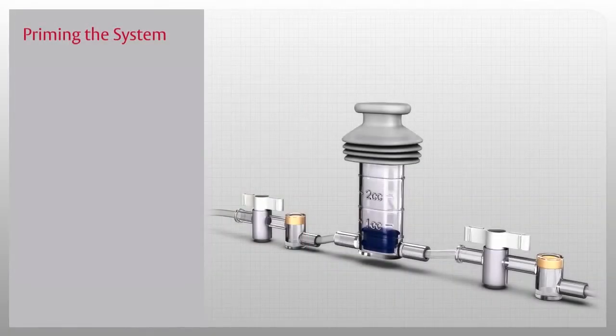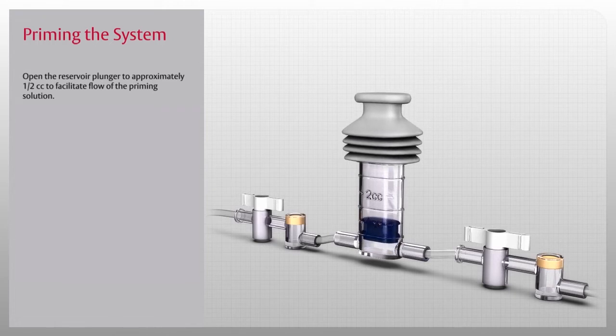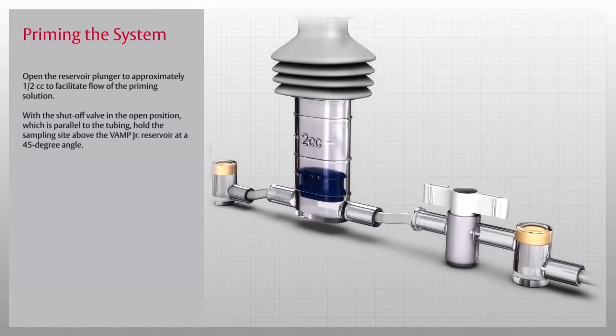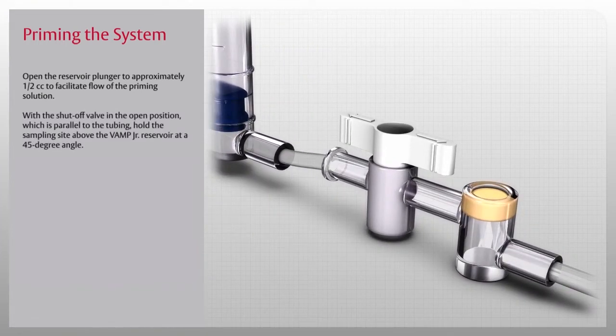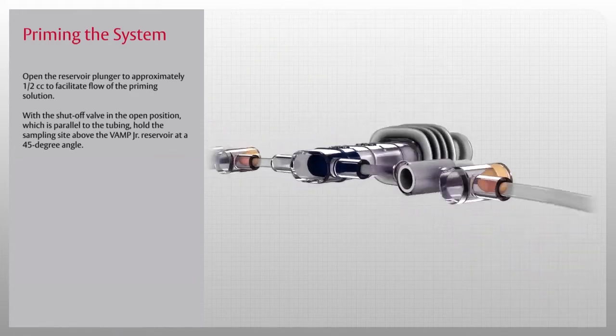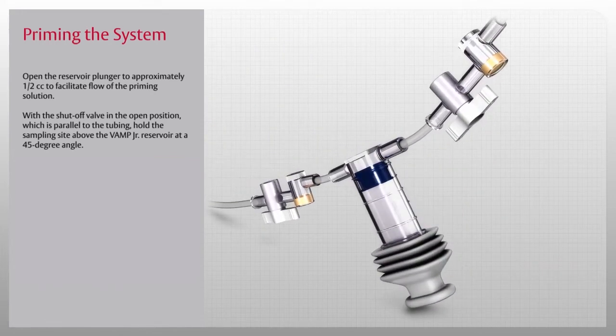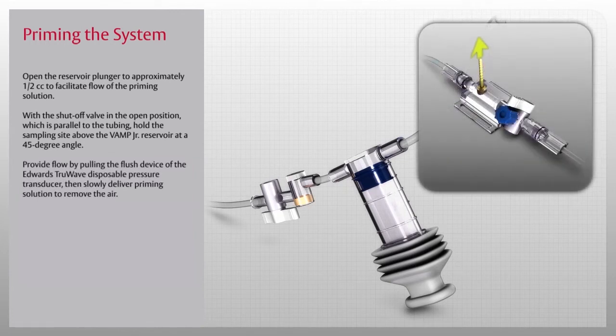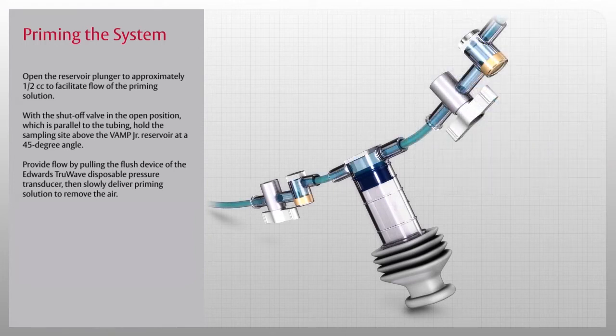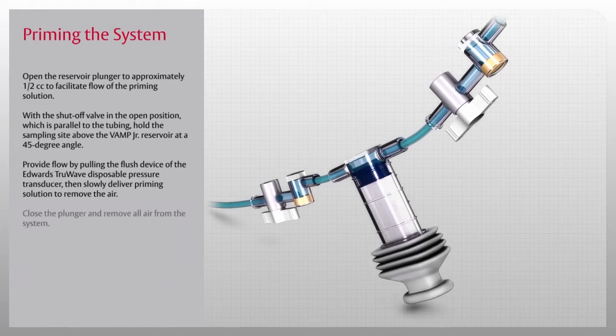Now that you have set up the VAMP Junior system, let's learn how to prime the system. First, open the reservoir plunger to approximately 1/2 cc to facilitate flow of the priming solution. Next, with the shutoff valve in the open position, which is parallel to the tubing, hold the sampling site above the VAMP Junior reservoir at a 45-degree angle. Now, provide flow by pulling the flush device of the Edwards TruWave disposable pressure transducer. Then slowly deliver priming solution to remove the air. When that is done, close the plunger and remove all air from the system.